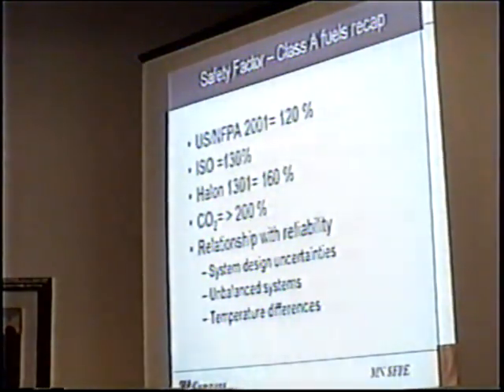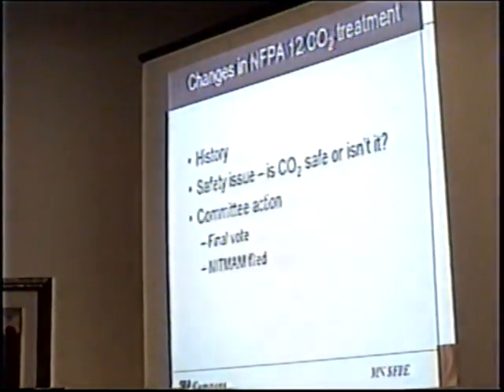So just to kind of recap, this is what you have for safety factors right now in the U.S. You have 120% of the extinguishing concentration, ISO is 130%, as compared with Halon, which is 160% as a minimum, and CO2, which is almost 200% minimum extinguishing concentration. And there's some issues associated with reliability, system design uncertainties, unbalanced systems, and so forth that provide some additional safety factors here. So, a little bit on CO2 here, then I'll turn it over to Todd for a second.